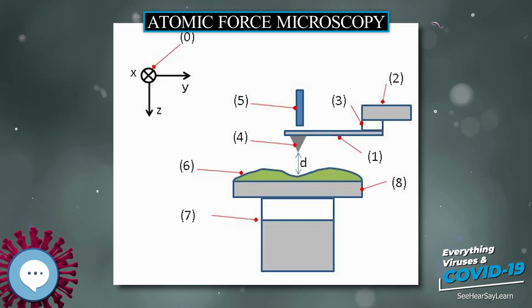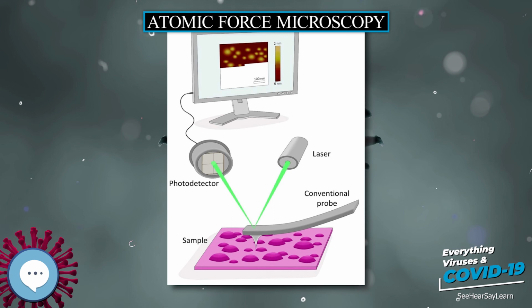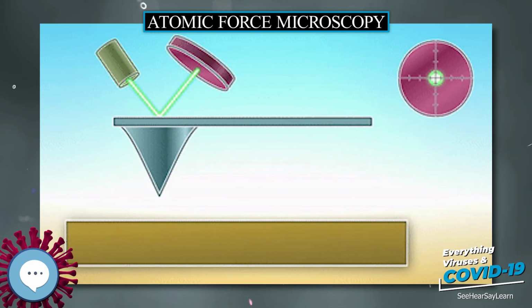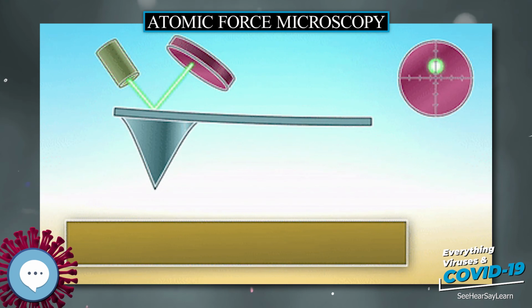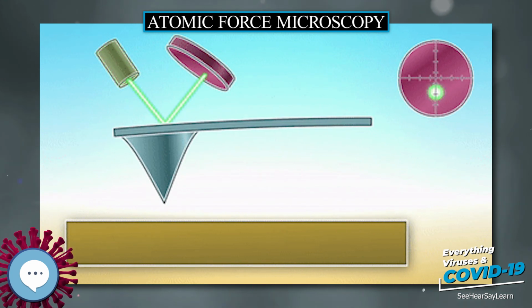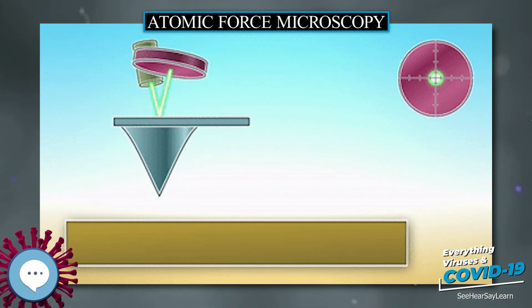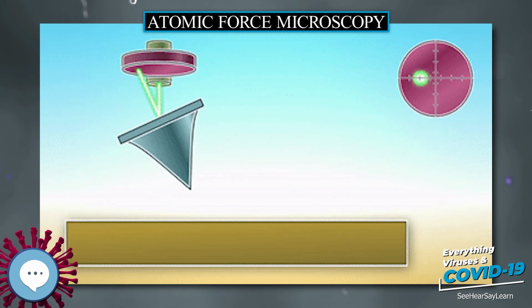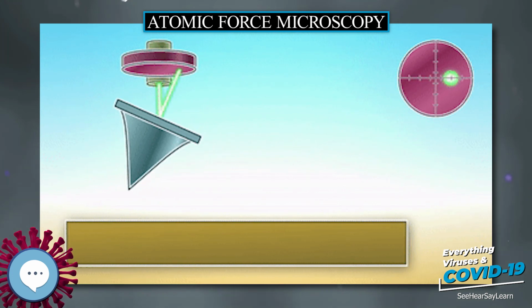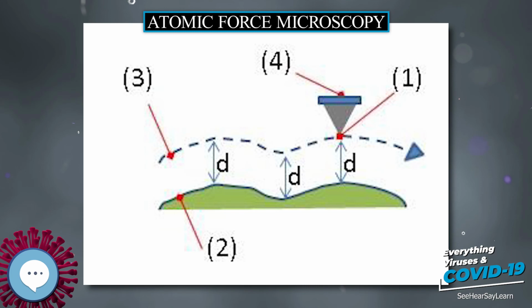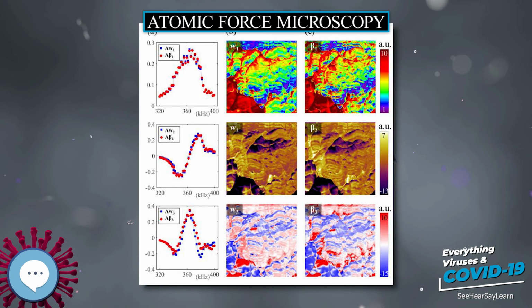Figure 3 shows an AFM, which typically consists of the following features. Numbers in parentheses correspond to numbered features in Figure 3. Coordinate directions are defined by the coordinate system, 0. The small spring-like cantilever, 1, is carried by the support, 2. Optionally, a piezoelectric element, typically made of a ceramic material, 3, oscillates the cantilever, 1. The sharp tip, 4, is fixed to the free end of the cantilever, 1.